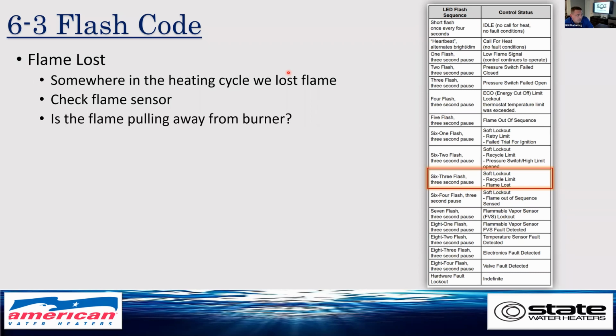If the flame is pulling away from the burner, we could have a situation where you don't have the restrictor installed at the end of the pipe, and the volume of air we're moving through that unit is too much. When that happens, we start to pull that flame away from that burner, which then could pull it away from the flame sensor, shutting down the unit. Check your flammable vapor switch. Was there a paint can that fell off into the room, or somebody spilled something? Are they refinishing floors? Is there a gas leak within the house? So there we have to go check the flammable vapor switch again. And remember, that causes a hard lockout, which means the gas valve will have to be reset.